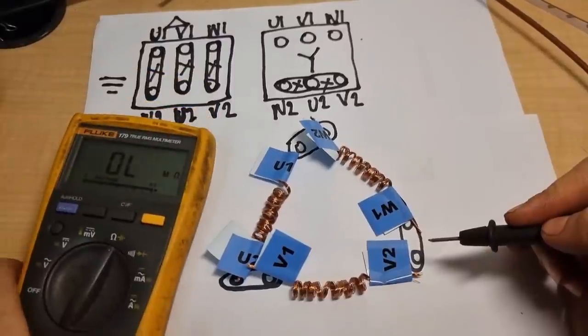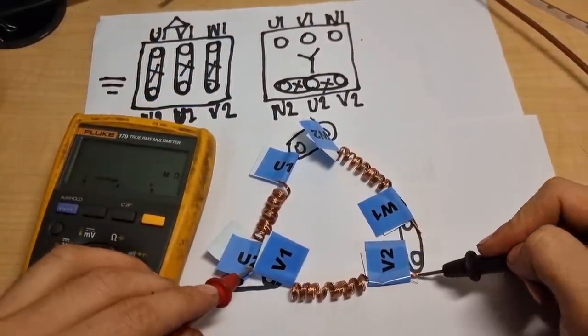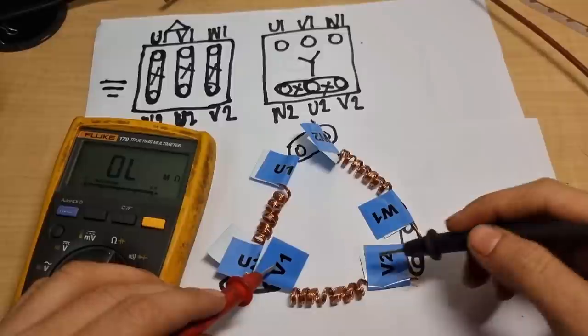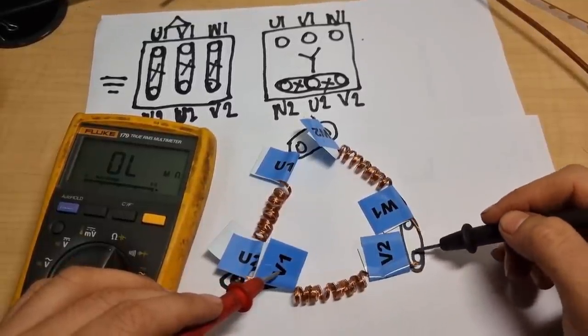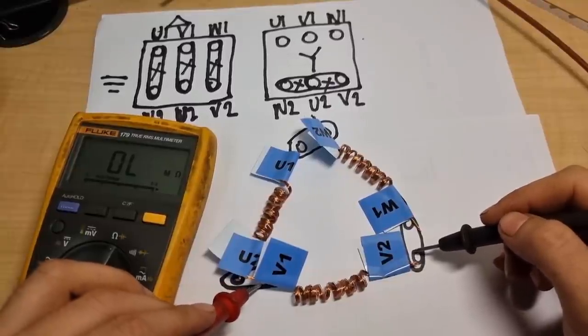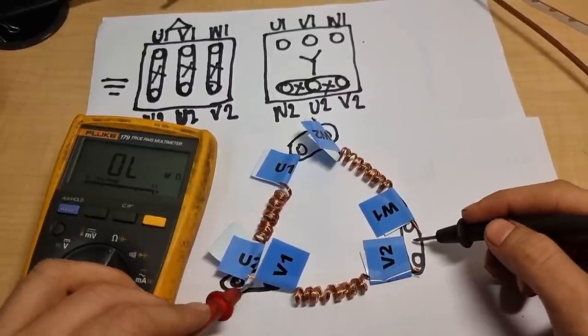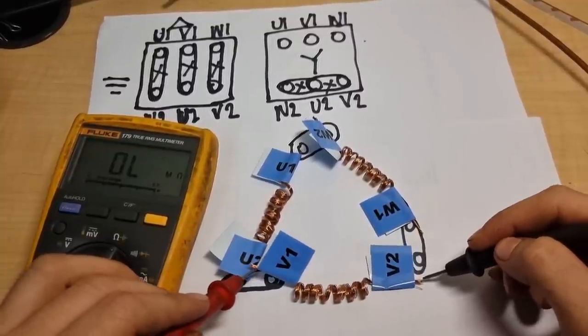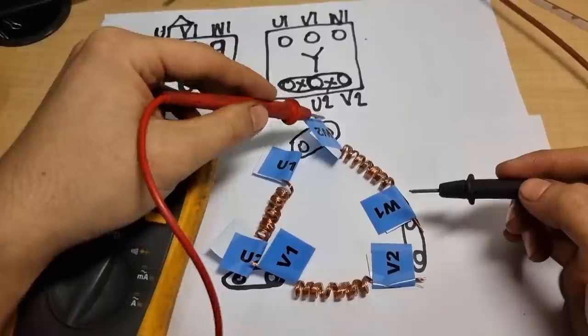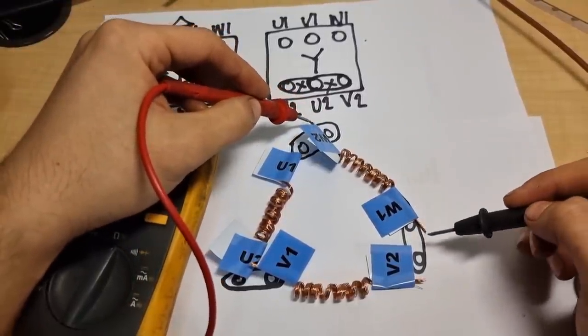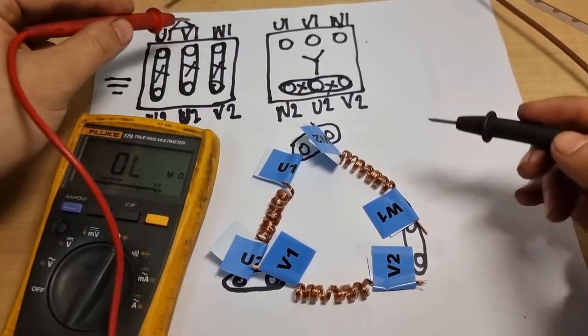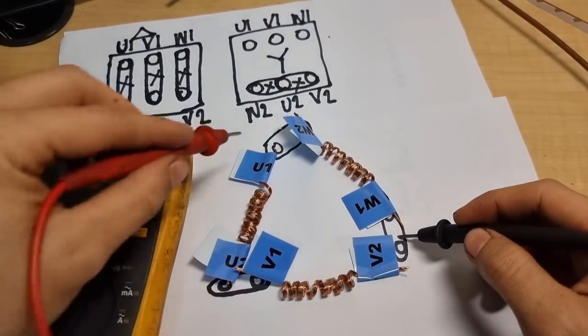This orientation is just like this. If I will measure now the V1 and V2, I am measuring the plate in between. It's the same, I'm measuring V1 and V2, but just like what I have said, sometimes the terminal or whatsoever that touches plate to plate, sometimes it's not the correct measurements that you are getting. That's why I'm removing them to have an exact measurement. I will have measurement from V1 to V2, which is V1 cable to V2 cable, end to end. Then you will have the W2 to W1 and the U1 and U2.